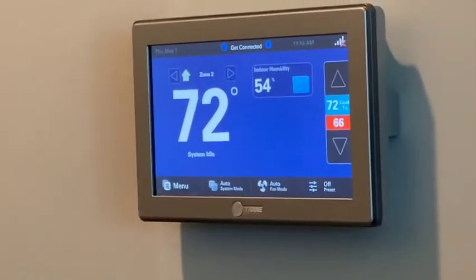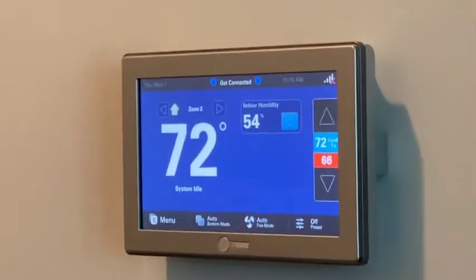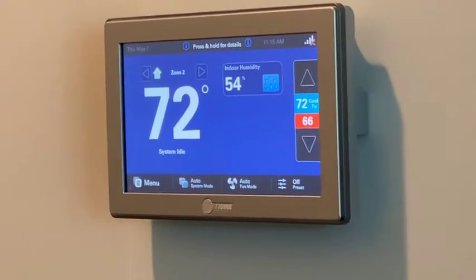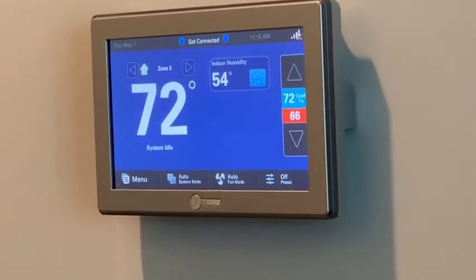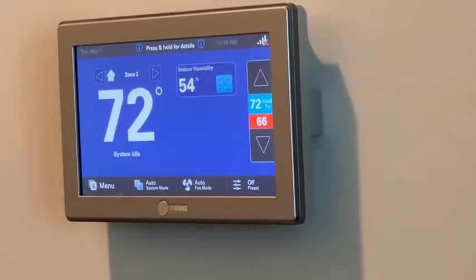You're breathing on it. I just want to see, because people say the air's not running. It's running bad because we have no load right now. So if the air doesn't run, it can't control the humidity. Oh, interesting. So that is one factor: on lax days like this, the humidity can creep up, because the air's not running.